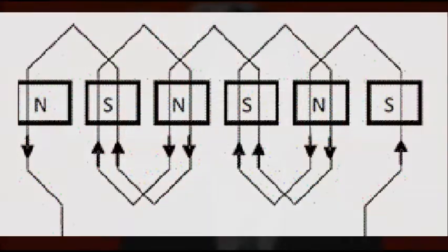If the coils are distributed over the whole armature periphery, then the armature winding of the alternator is referred to as whole-coiled winding. As shown in the following figure, it is a double layer winding, where one side of each coil is placed on the top of the armature slot while the other side is placed in the bottom of the slot, represented by dotted lines. Hence it is essentially a double layer winding.